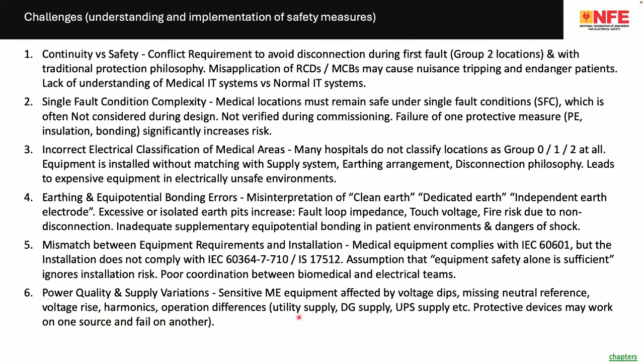In a typical hospital in India, we have the electricity supply from the distribution company, from the transformer, from the diesel generator, from the UPS, three different impedances. With the impedance mismatch, sometimes protective devices may not work. When the supply is coming from the transformer, of course, the protective devices are capable of tripping, whereas when the supply is from a UPS, the same MCB is not able to trip, which will result in a fire.